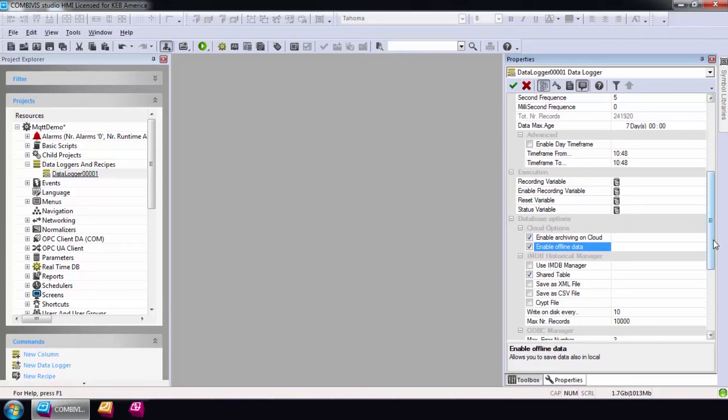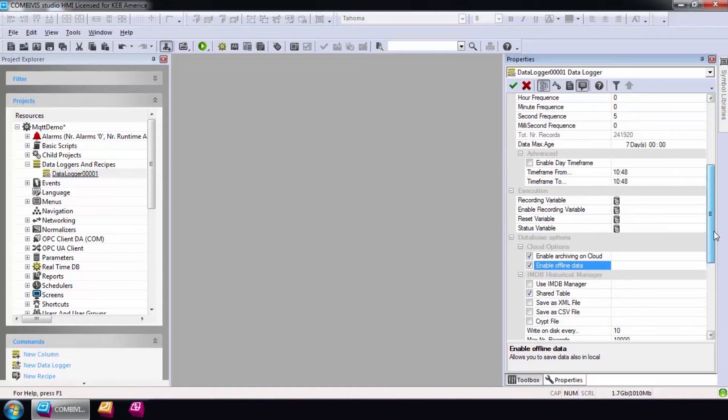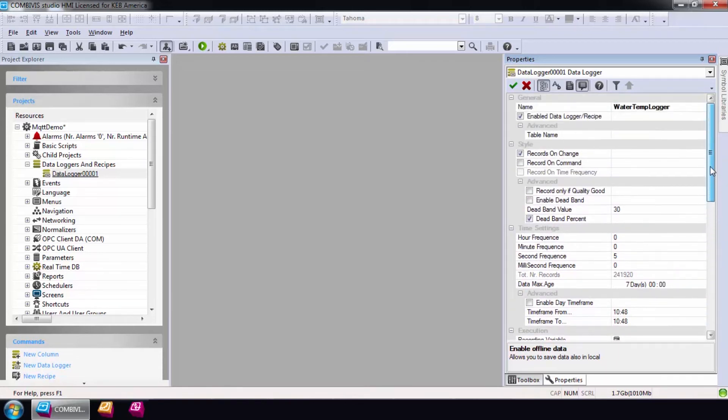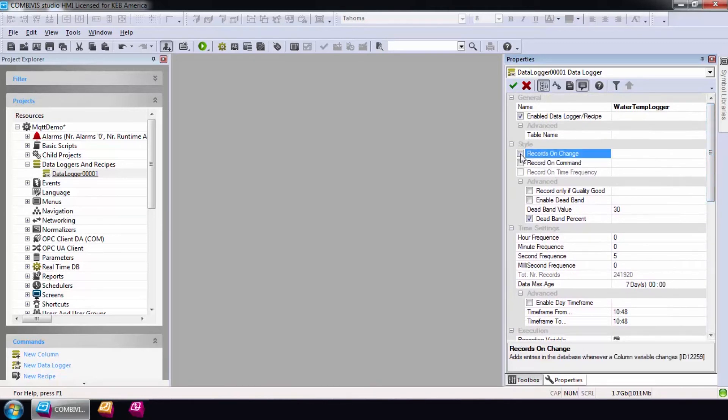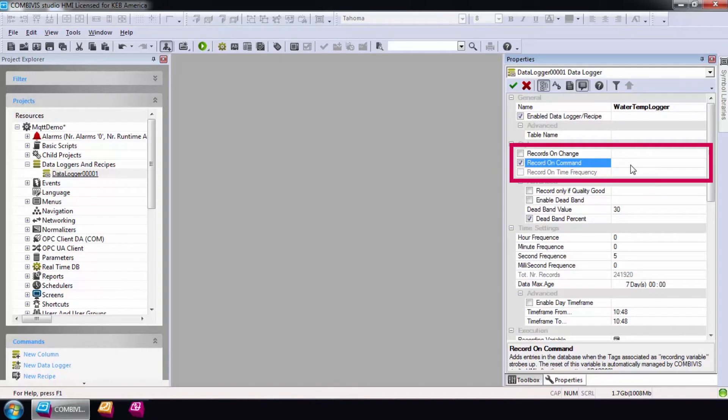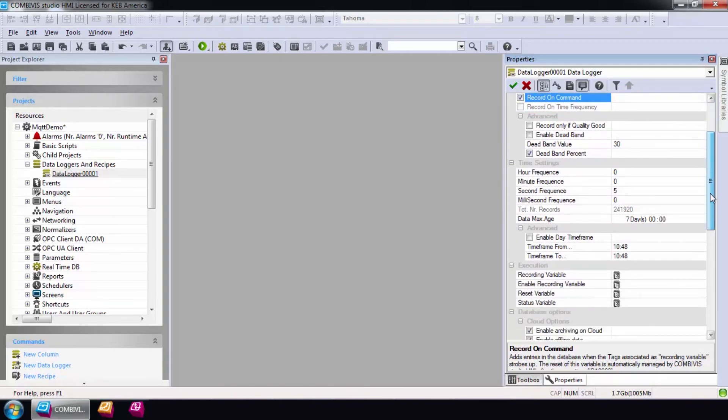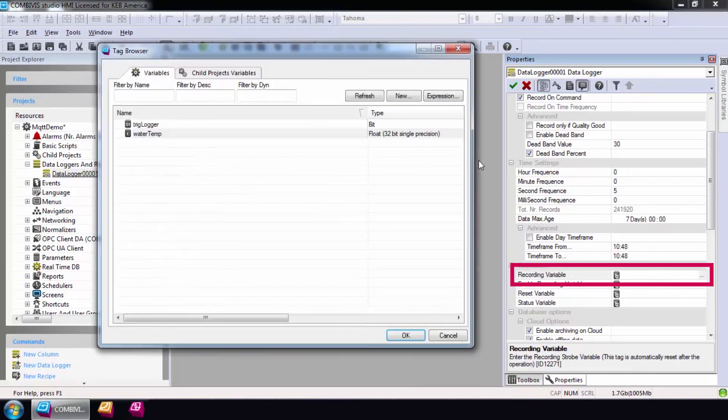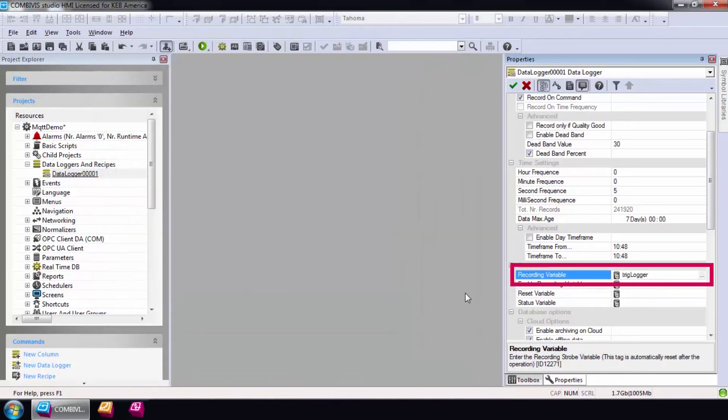The final step in configuring the data logger is to determine how and when to add data to the data logger. Data can be recorded whenever a tag value changes using the records on change option or using a rising edge trigger bit with the record on command option. My PLC program will trigger the recording value every six seconds, and the data logger will automatically set the trigger back to false. Therefore, I will check record on command and enter the trigger in the recording variable.